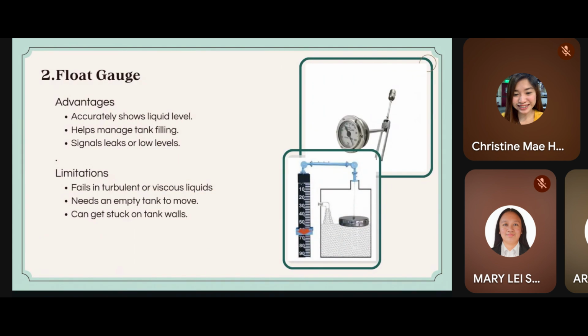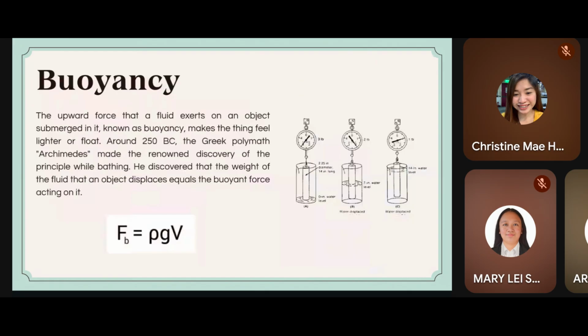For the float gauge advantages and limitations, first the advantages: it accurately shows liquid level, helps manage tank filling, and signals leaks or low levels. For the limitations: fails in turbulent or viscous liquids, needs an empty tank to move, can get stuck on tank walls. Next slide, please.